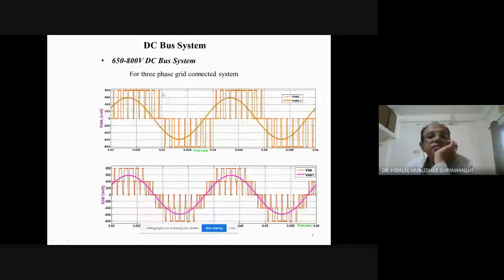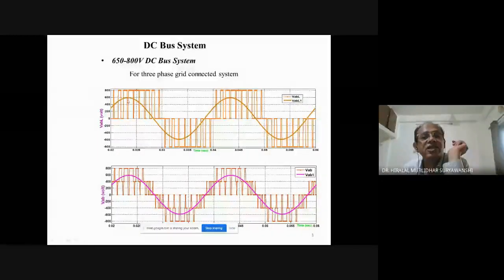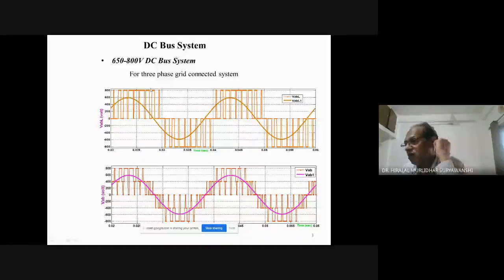Now, it's clear why 800 volt, because this is 415 multiplied by √2. It is the peak; the RMS value is 415. Remember, multiplied by √2 gives a peak of 600 volt. To get the peak value of 600 volt, you need an 800 volt DC bus. So the inverter output will be 800. But if you take the average of the inverter output voltage, you will get this sine wave, the line to line voltage of the 3-phase inverter. Then you are able to connect.